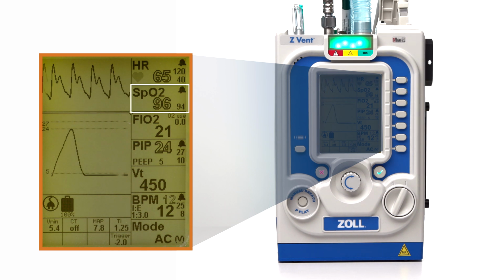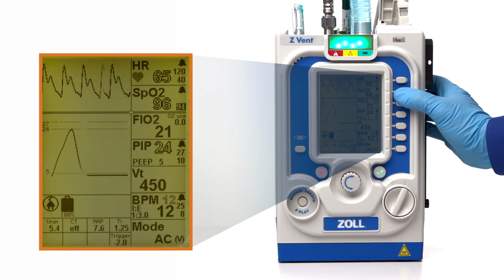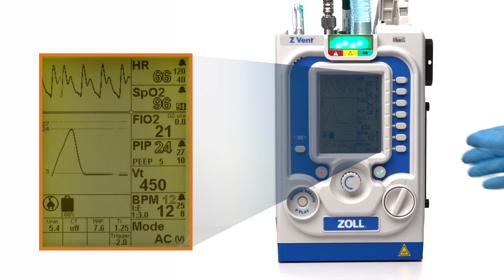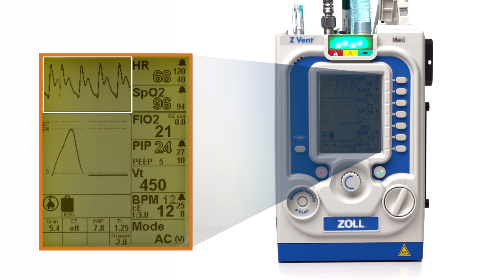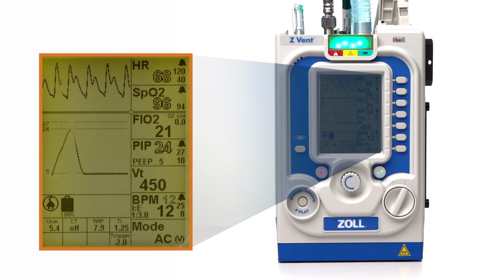The second parameter window is pulse oximetry, or SpO2. The outlined text represents the patient's current measured SpO2 level. The low alarm defaults to 94% SpO2. Press the parameter button once to change the low alarm limit. When a pulse oximeter is used, the pleth waveform is displayed in the waveform window directly to the left.